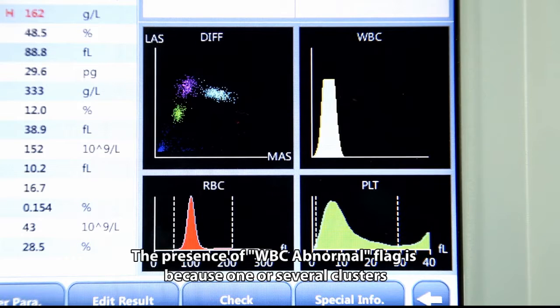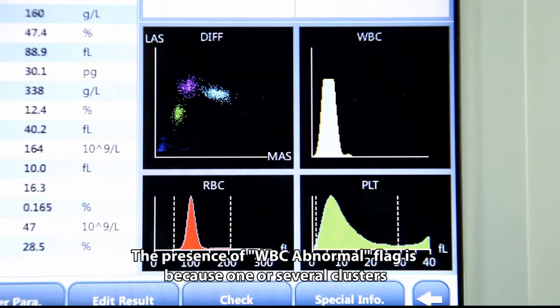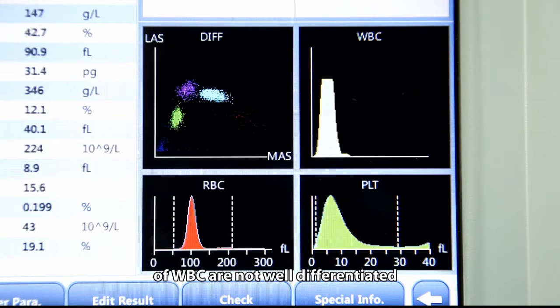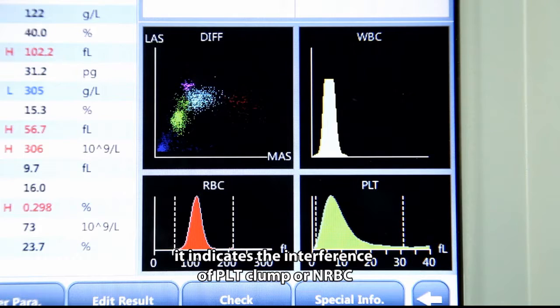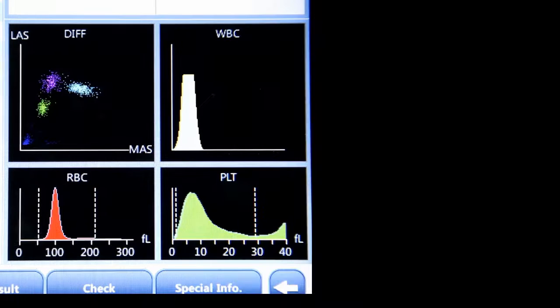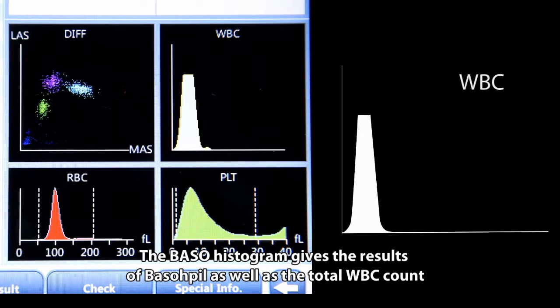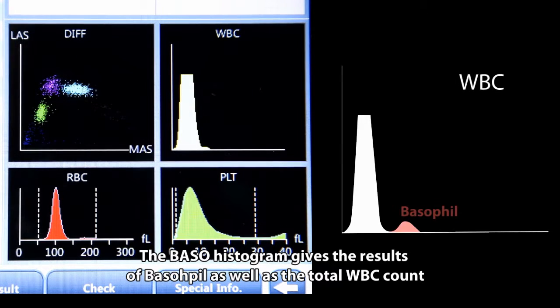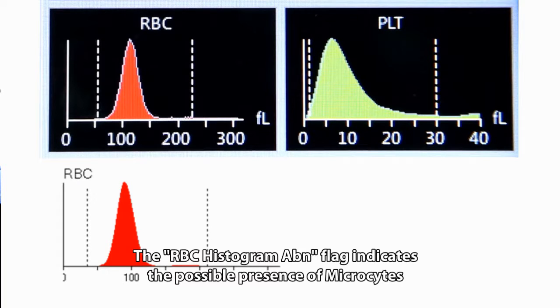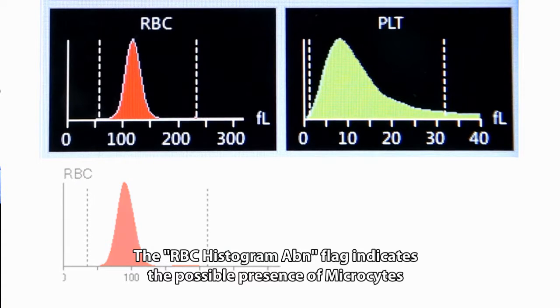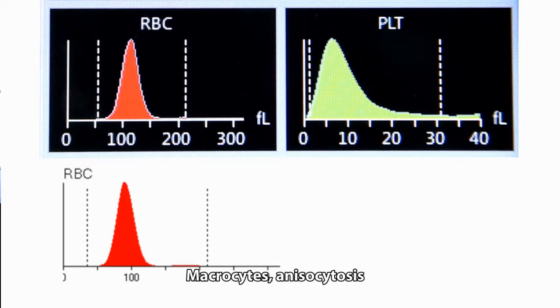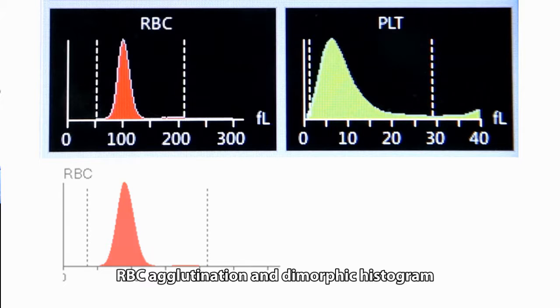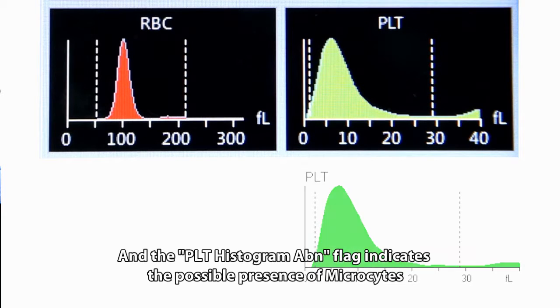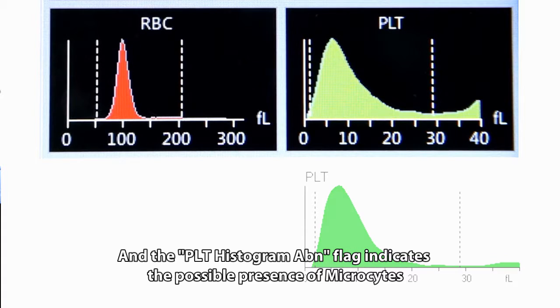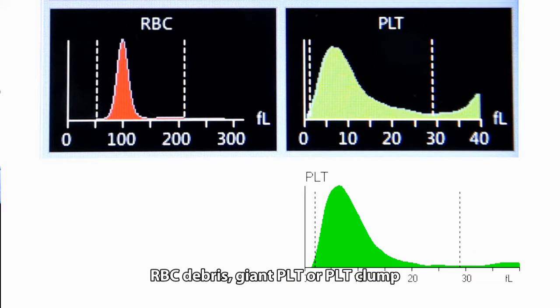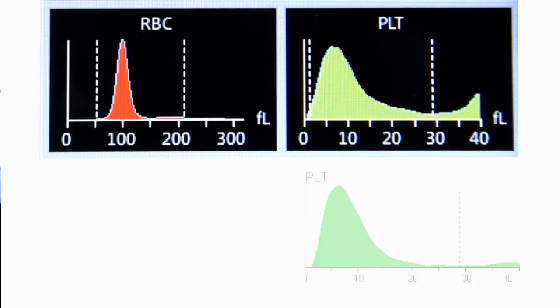The presence of the WBC abnormal flag is because one or several clusters of WBC are not well differentiated. It indicates the interference of PLT clump or NRBC. The baso histogram gives the results of basophil as well as the total WBC count. The RBC histogram ABN flag indicates the possible presence of microcytes, macrocytes, anisocytosis, RBC agglutination, and dimorphic histogram. And the PLT histogram ABN flag indicates the possible presence of microcytes, RBC debris, giant PLT or PLT clump.